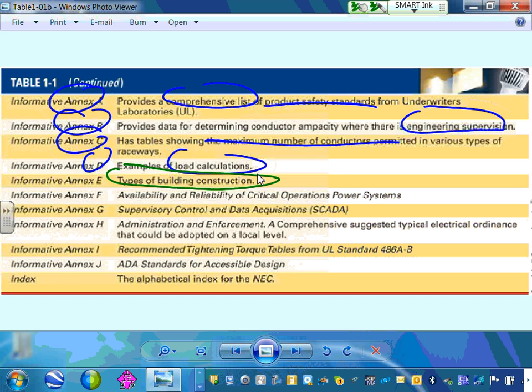This is what makes you an expert when they talk about construction—type of building construction, type 1 or type 5. Type 5 is wood, type 1 is typically concrete or steel. Do you think when we have a wood building we use the same wiring methods as a concrete building? No. You can't use Romex in a concrete or steel building unless you put it inside an EMT conduit like these. Who in his right mind would put Romex in an EMT conduit here? So anyway, construction type is very important, especially if you work for an engineering firm.